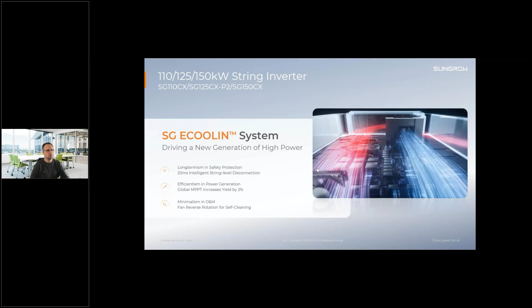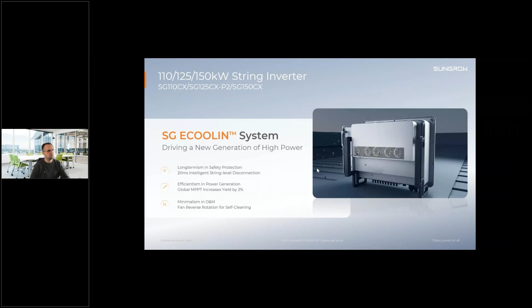Now we go to our string inverter, the most powerful one. It is the SG150CX. It has an ECOOLIN cooling system, which allows it to work intelligently, cool down, and clean its fans, which allows us to minimize O&M. This actually means that, as you can see in the visualization, the fans can run in reverse. They start running in reverse once per day, so they can clean up and pull out the debris, or push out the debris in this case. It also has 20 millisecond intelligent string-level disconnection, in case there is a problem with the string.